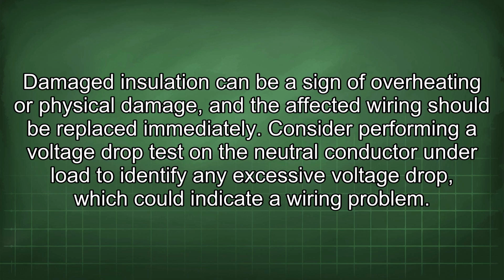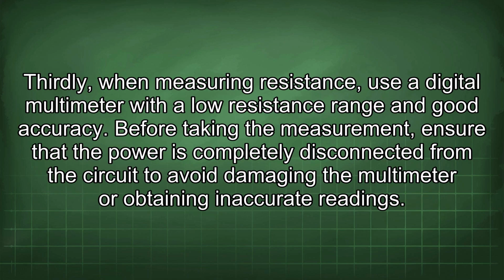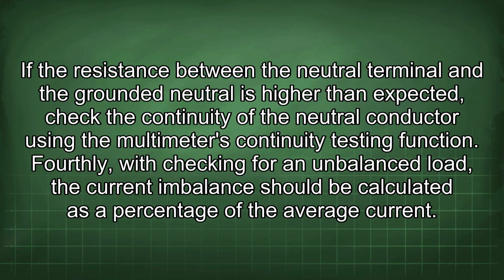indicate a wiring problem. Thirdly, when measuring resistance, use a digital multimeter with a low resistance range and good accuracy. Before taking the measurement, ensure that the power is completely disconnected from the circuit to avoid damaging the multimeter or obtaining inaccurate readings. If the resistance between the neutral terminal and the grounded neutral is higher than expected, check the continuity of the neutral conductor using the multimeter's continuity testing function.